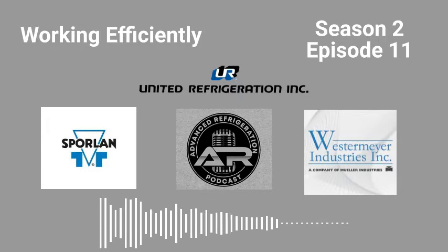Appion makes these Speedwise fittings, which are great. If you haven't checked them out, do it. True Tech Tools is the only place I've seen them. It's a Y that'll go 3/8, 3/8, 3/8 — two male 3/8 down to female 3/8. They also have a 1/2 inch female to two 3/8, and a 1/4 inch to two 3/8. This lets you use bigger hoses and pull from multiple spots.